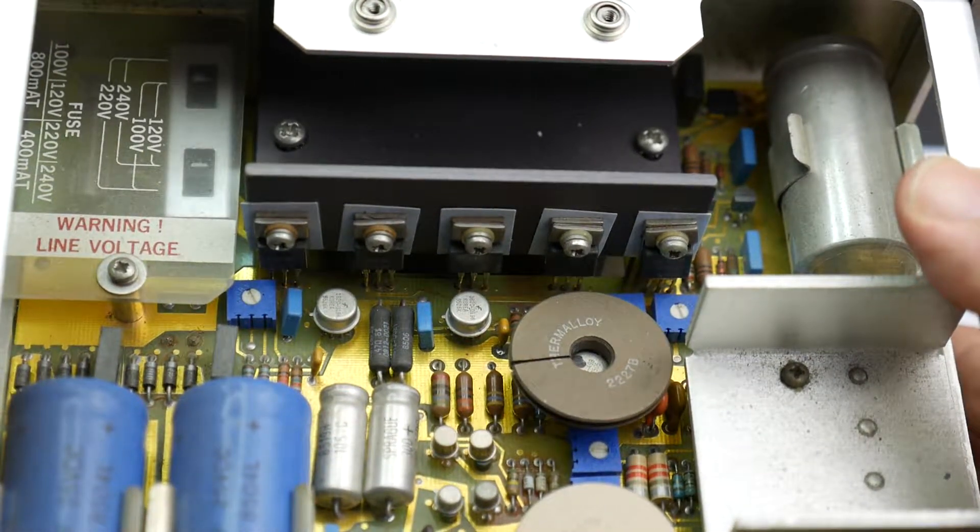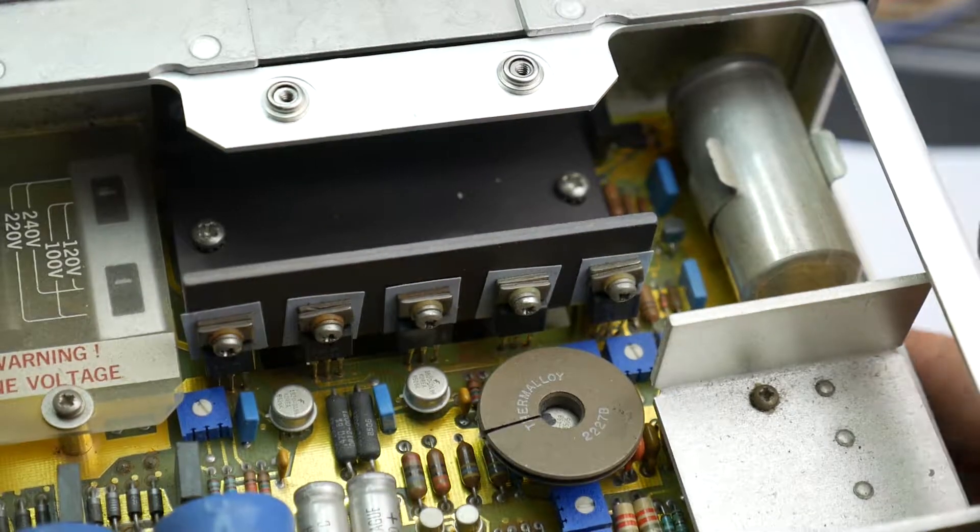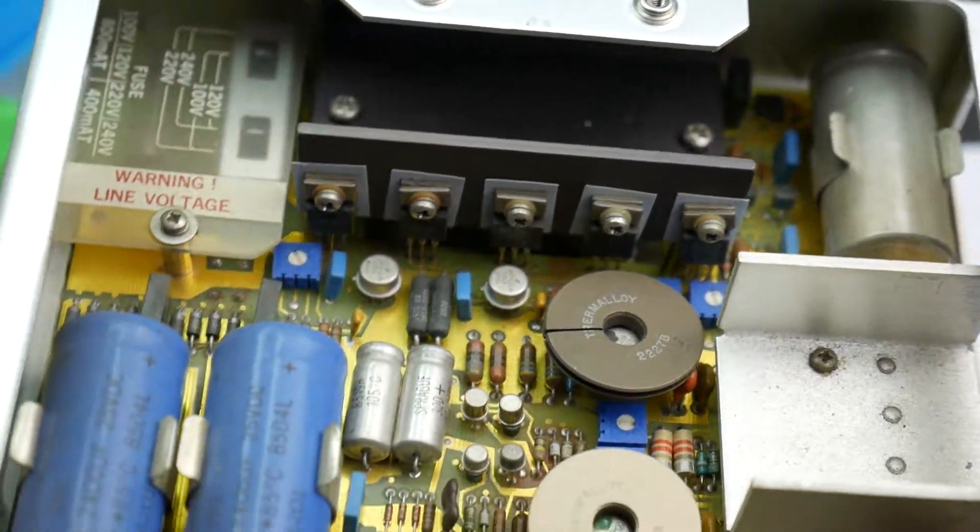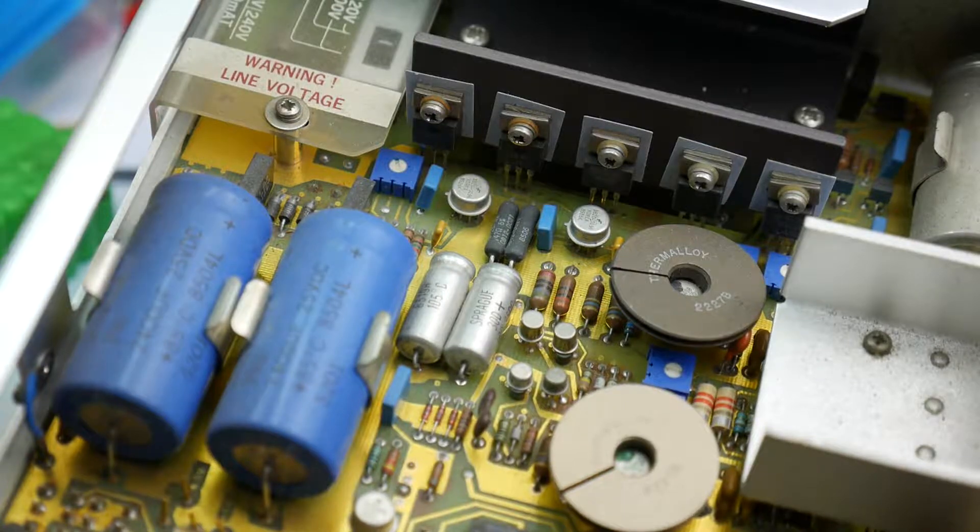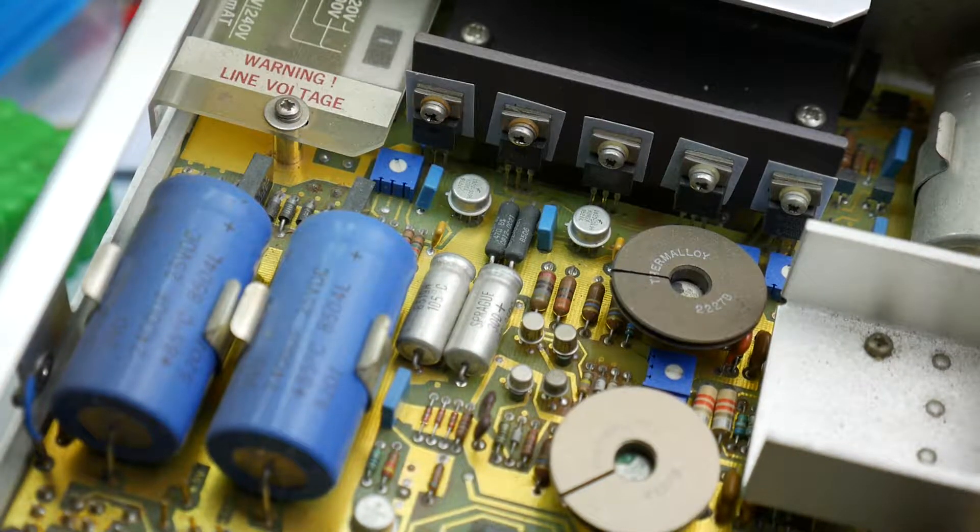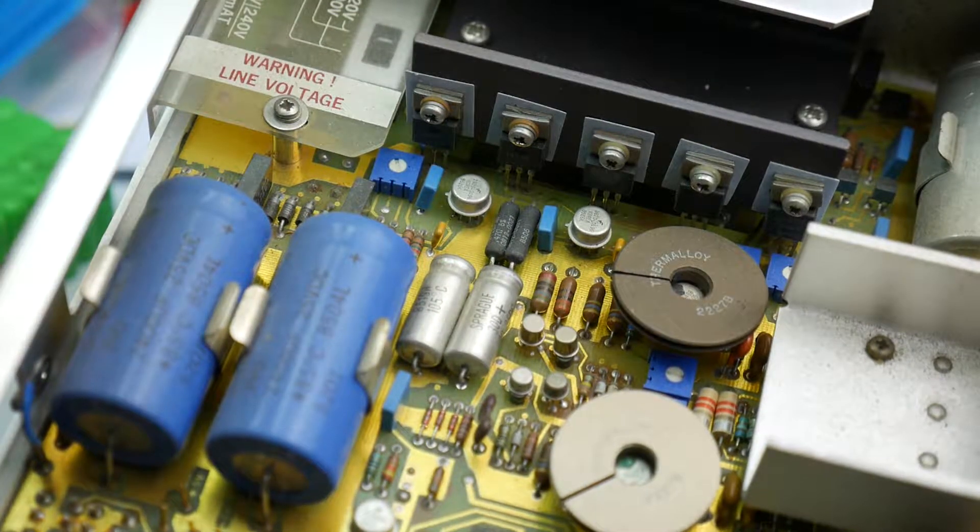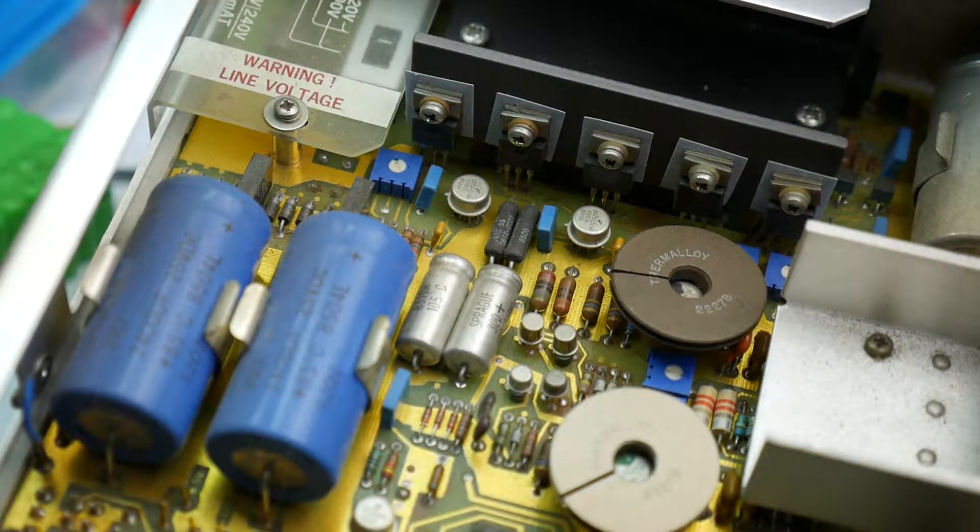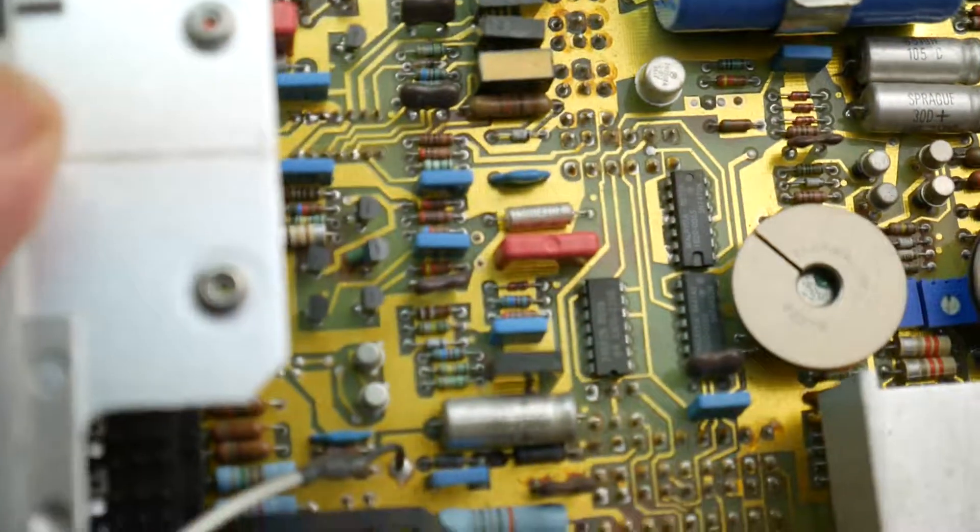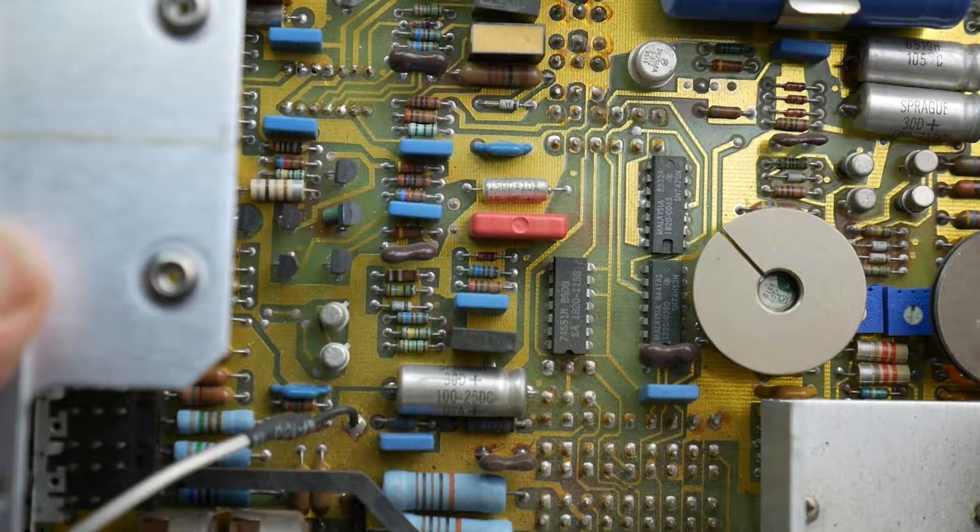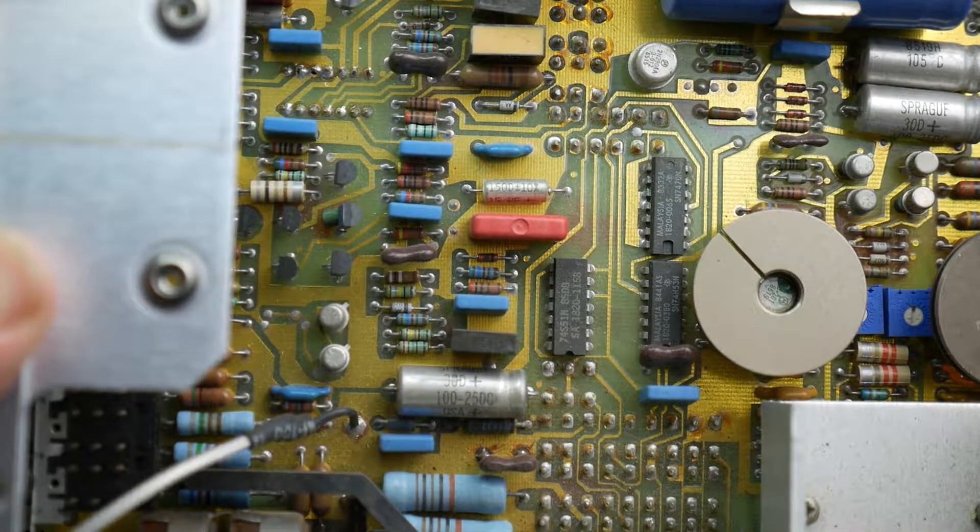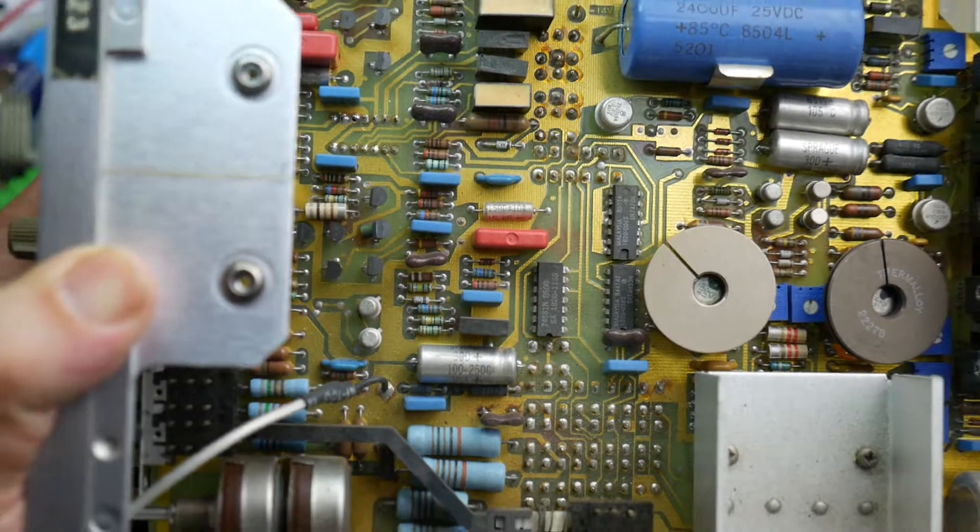There's our power supply circuit and the big capacitor in the side here. These are all things that need to be just looked at to make sure they're not bulging or anything like that. These sort of things do sometimes suffer just from age and so they may have to be replaced. But of course we only replace them if they're actually faulty. I'm not going to replace them if they're actually okay.